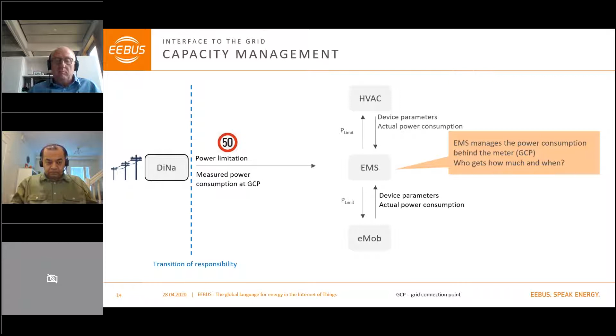Another use case regarding interfacing to the grid is tariff-optimized operation, or maybe better to say, interfacing to the market. In this use case, the EMS receives incentive tables which it distributes further to the EEBUS devices in the building. Based on the incentive table and device energy demand, a negotiation takes place, and as a result a consumption plan is set. Based on this consumption plan, the EMS controls the devices. And if incentives or demand changes, a new negotiation is triggered.